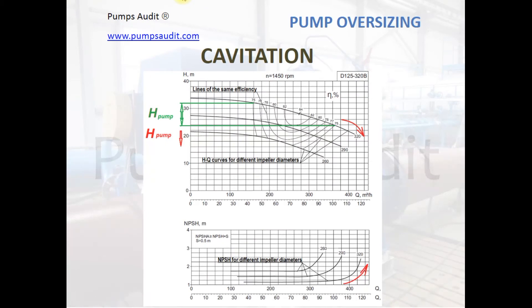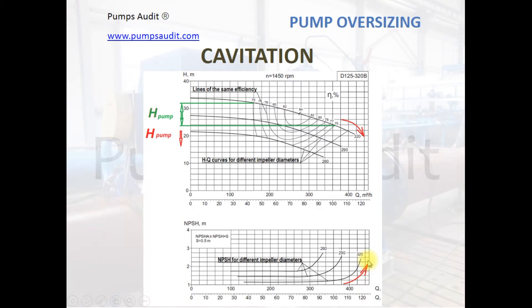Cavitation is also a sign of pump oversizing. When the pump operates beyond the right border of the allowable operating range, the NPSH required of the pump grows rapidly. The presence of cavitation erosion on impellers can indicate that the pump is oversized.